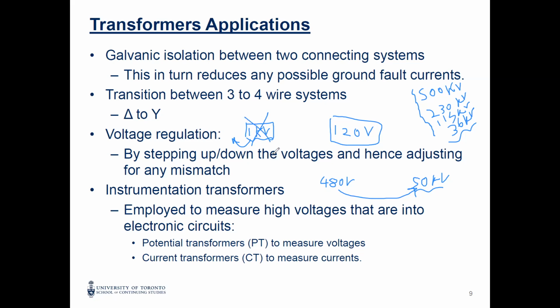It depends on the system. You are talking about the transmission. In Ontario at least, this is 500, 230. They are the backbone of the system. 115 is a kind of sub-transmission, we call them, systems, okay? Lower than this, then it means you reach the distribution level.